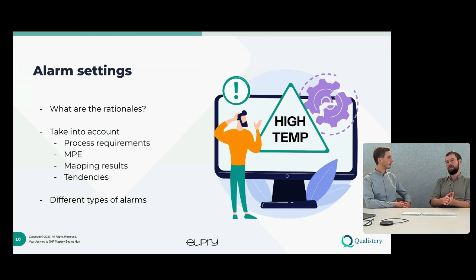One of the things we see, I would say a pitfall, is that if you have a fridge from 2 to 8 degrees, you will set the critical alarms at 2 and 8 degrees. But that also means that you have 0 time to respond. So if you measure 8.5 degrees suddenly, it's already too late. Is that a risk you're willing to take? And what is the average response time? Let's say a Friday night at 9 o'clock in the evening. What is the response time from you getting that alarm to you actually doing something about it?